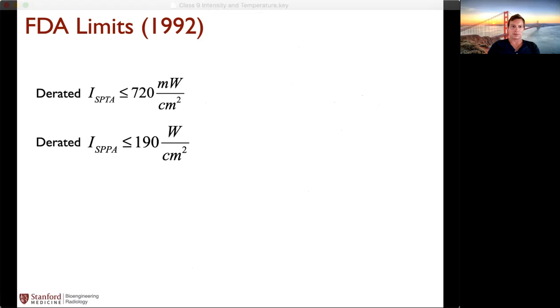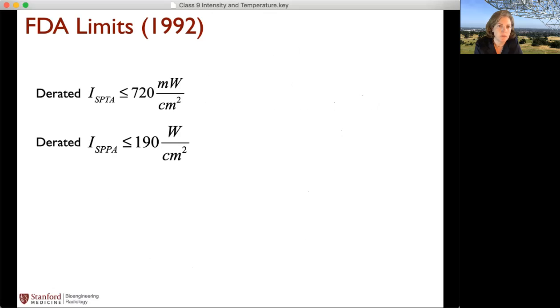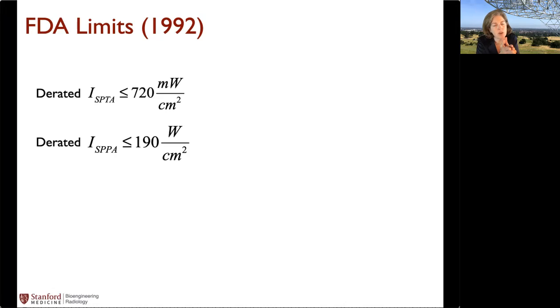Getting back to the FDA limits, these are limits for imaging that were set back in 1992. And the limits that they set for imaging were that the derated ISPTA had to be less than 720 milliwatts per centimeter squared, and the derated ISPPA had to be less than 190 watts per centimeter squared. Sorry, this is in milliwatts, and then this is in watts. So of course, if you're going to do imaging, your pulse average is going to be much larger, because you're going to do a pulse, and then you're going to do the rest of the image, and then you're going to come back to that area. So at any one location, that's much, much lower temporal average, because there's all that time period that you're imaging other parts of the image.